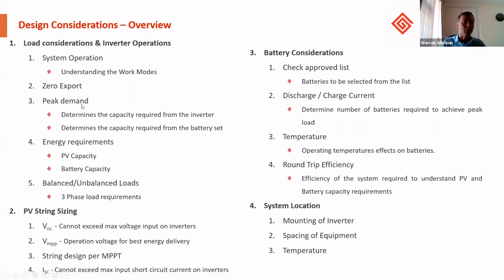We're also going to be looking at the peak demand. We need to understand the capacity required from the inverter and the batteries so that we can deliver to the load. We need to understand the energy requirements. So we'll be looking at the sizing of the PV array and the sizing of the batteries. And then we'll be illustrating the balanced and unbalanced loads on ET inverters. For string sizing, the most important aspects we're going to talk about are open circuit voltage, maximum power point voltage, the string design, the MPPT, and the short circuit currents.